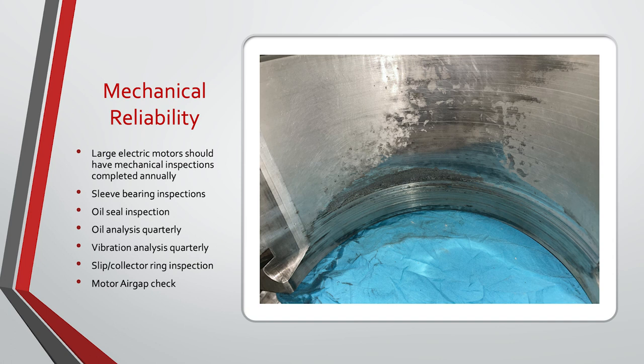Mechanical reliability is what this is all about. We talk about being reliable and what keeps us reliable. One of the big things we see with larger medium voltage motors is people saying 'it was running fine until it wasn't.' A lot of times people will not do oil samples — something as simple as having a tap on your oil sump so somebody can walk around, collect a small bottle of oil, send it out, and get it analyzed. Doing something that simple tells you whether you're having bearing deterioration, whether you have Babbitt or particles in the oil. I recommend doing this once a year: crack those bearing cases open, roll the bearings out, do an oil seal inspection.